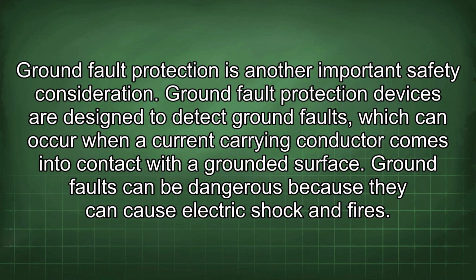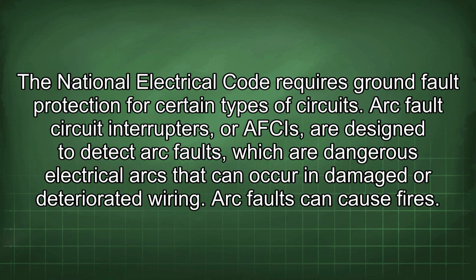Ground fault protection is another important safety consideration. Ground fault protection devices are designed to detect ground faults, which can occur when a current carrying conductor comes into contact with a grounded surface. Ground faults can be dangerous because they can cause electric shock and fires. The National Electrical Code requires ground fault protection for certain types of circuits.